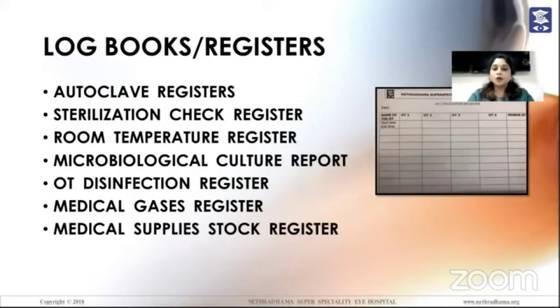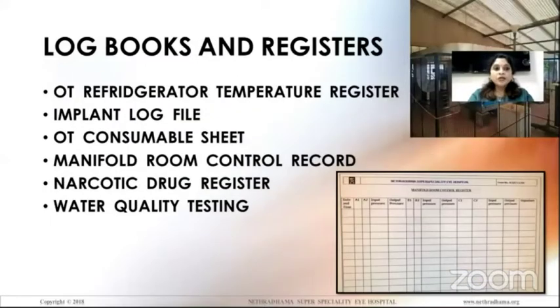Coming to the logbooks and registers that have to be maintained, they could be either in soft copy or hard copy. If authorization is required, it should be in hard copy, like the autoclave registers, sterilization check register, room temperature register, microbiological culture report, OT disinfection register, medical gases register, medical supplies stock register, OT refrigerator temperature register, implant log file, OT consumable sheet, manifold room control record, narcotic drug register, and water quality testing. These are the records we maintain, and there can be some modifications in the names we give, but these have to be maintained.